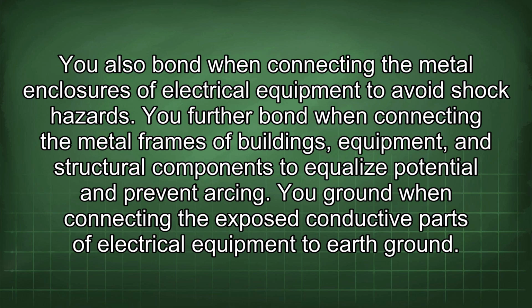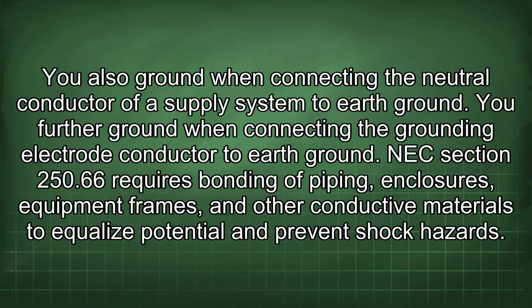You further bond when connecting the metal frames of buildings, equipment, and structural components to equalize potential and prevent arcing. You ground when connecting the exposed conductive part of electrical equipment to earth ground. You also ground when connecting the neutral conductor of a supply system to earth ground. You further ground when connecting the grounding electrode conductor to earth ground.